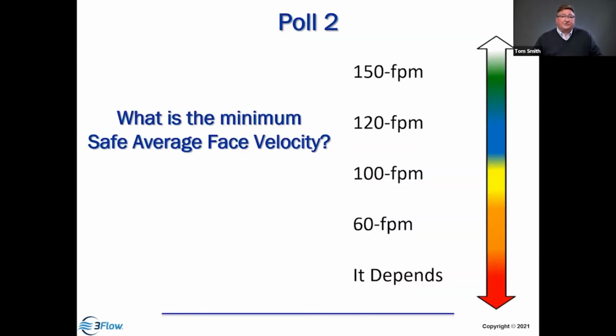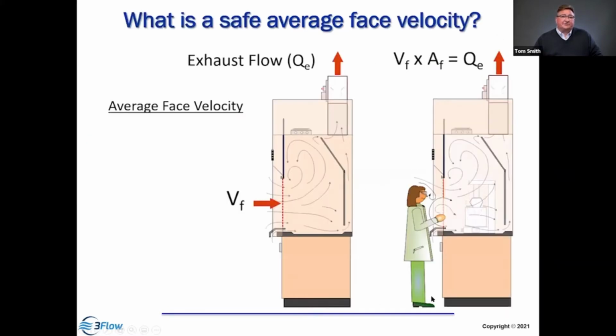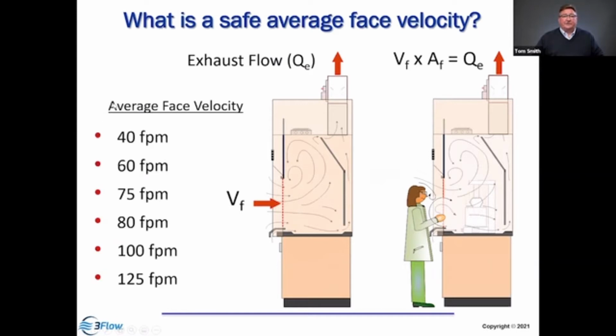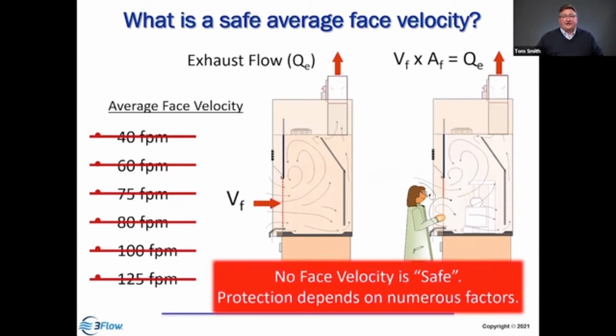So you've already answered this question, and it came back about equal 100 feet per minute, and it depends. So let's look at this answer in a little more detail. What is the safe average face velocity? Well, velocity is the speed of the air entering the hood. When we look at different specifications, what we find is that there is no velocity that is necessarily safe. We have not taken into account the occupant, the type of work they're doing, and the containment requirements. The velocity is just the speed of the air entering the hood.